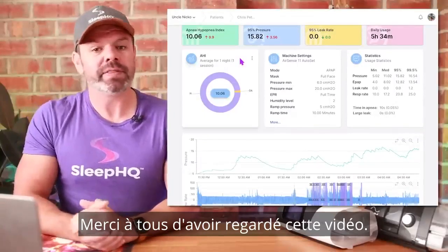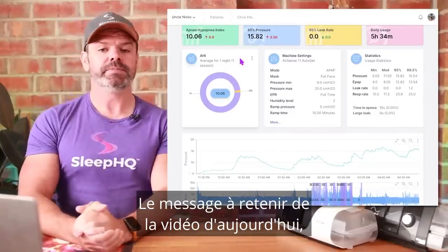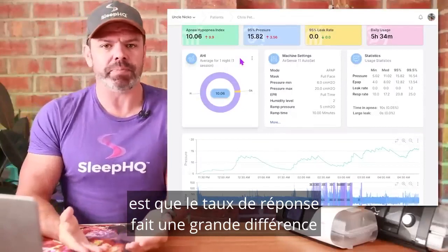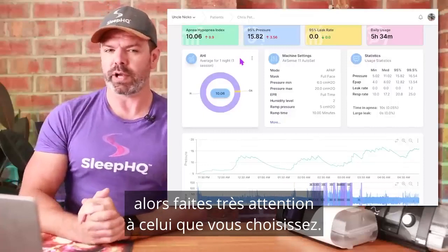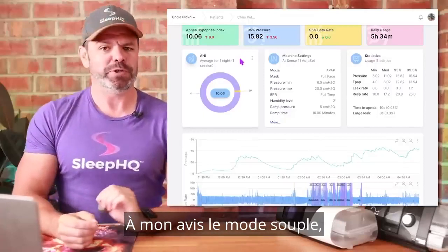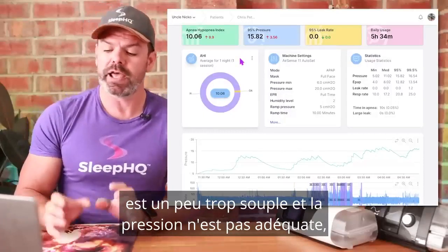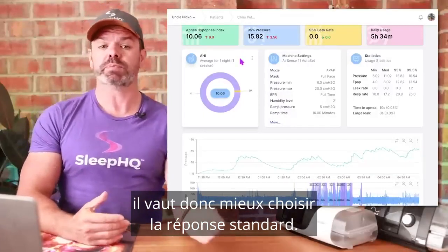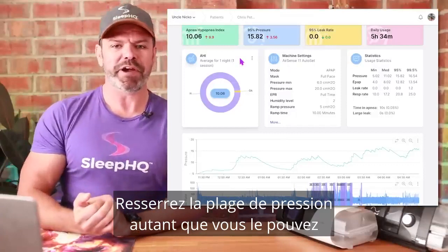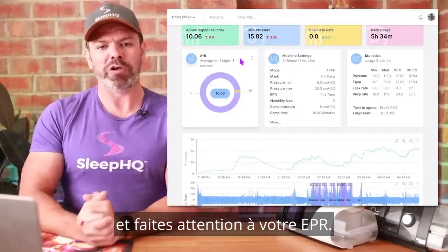Thanks for watching, everyone. The take-home message from today's video is the response rate does make a big difference to your results. So be very careful which one you choose. In my opinion, the soft is a little too soft, and the pressure is not adequate. So you're much better off choosing the standard response. Tighten up that pressure range as much as you can, and be mindful of your EPR.